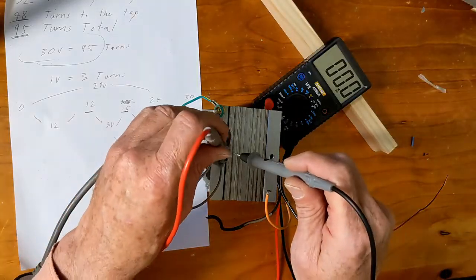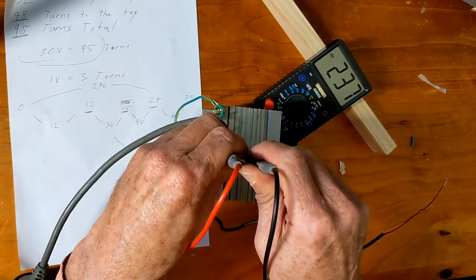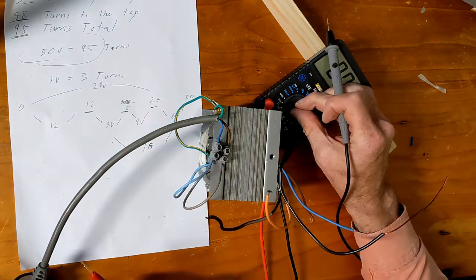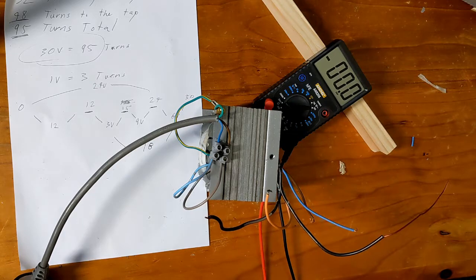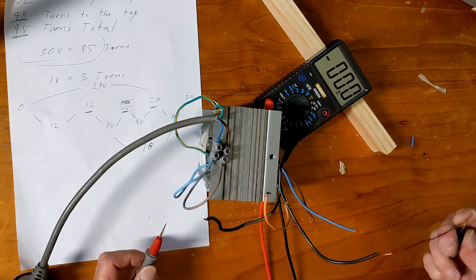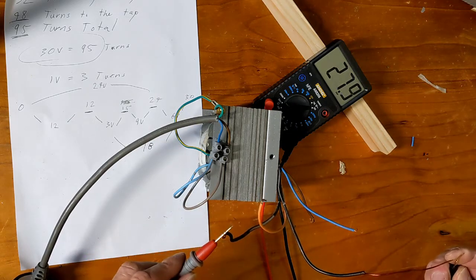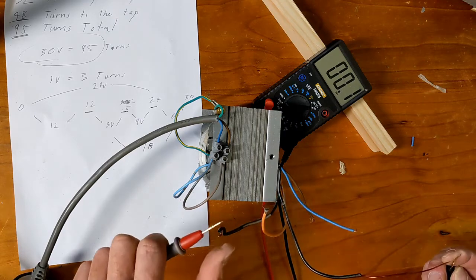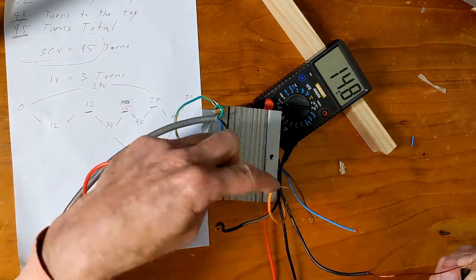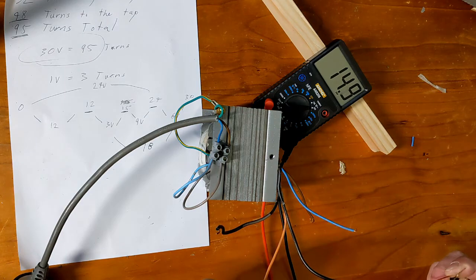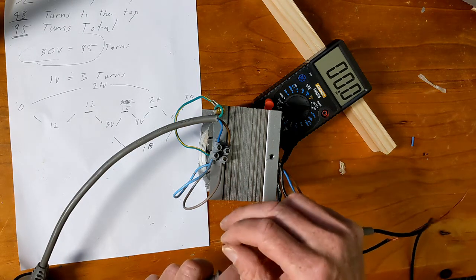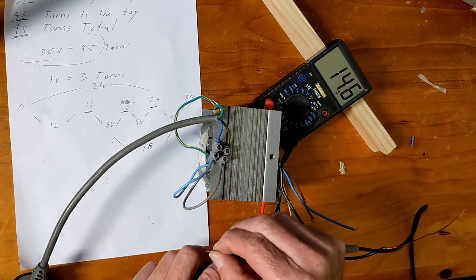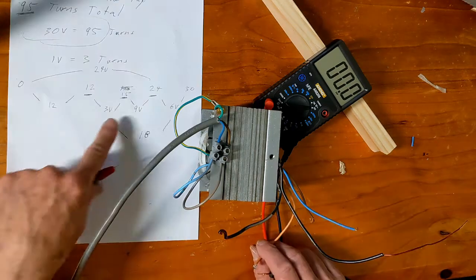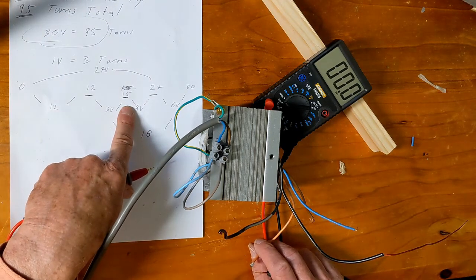On the line side, we've got 237 volts. On the low voltage side, testing between one leg and the other, we have 30 volts. Going to that centre tap, we should have 15 volts, and that's pretty close. Looking at the other side, we've got 15 volts - pretty close. I'll use that 15 volts as my reference point.